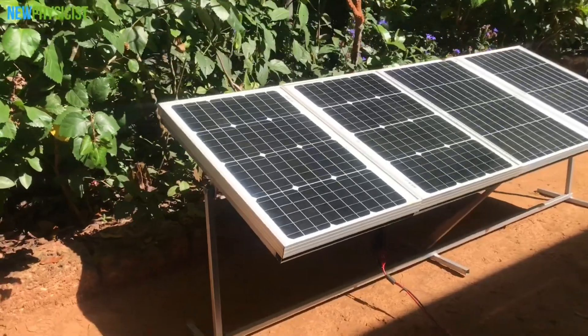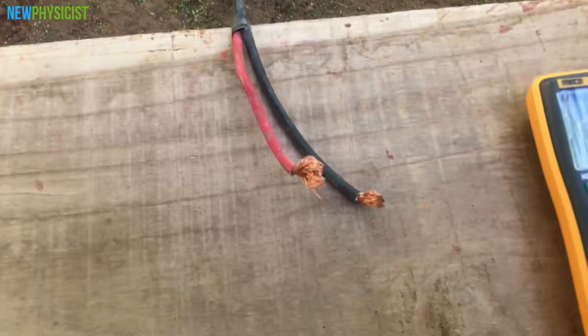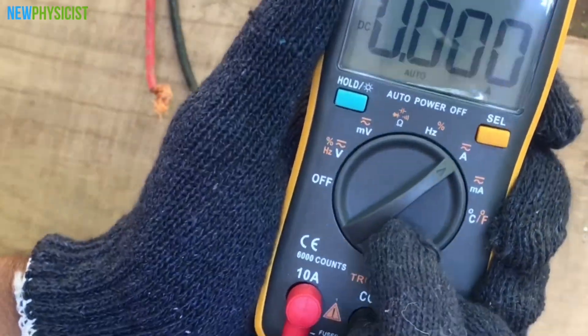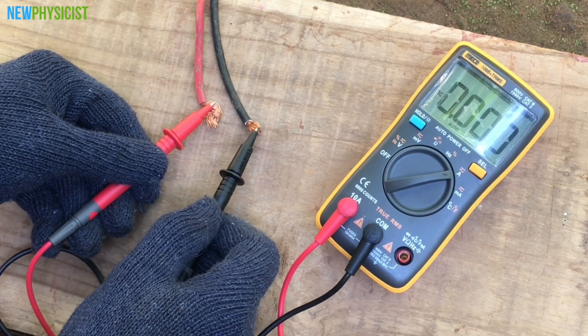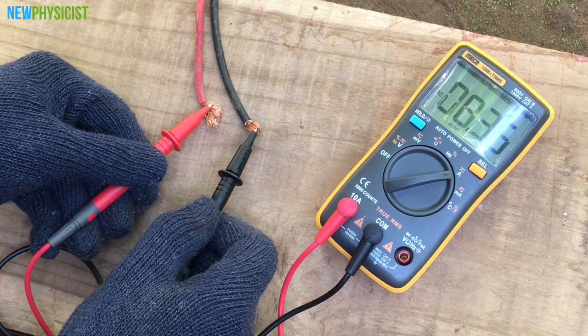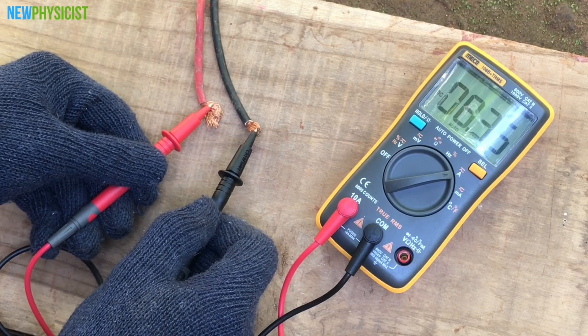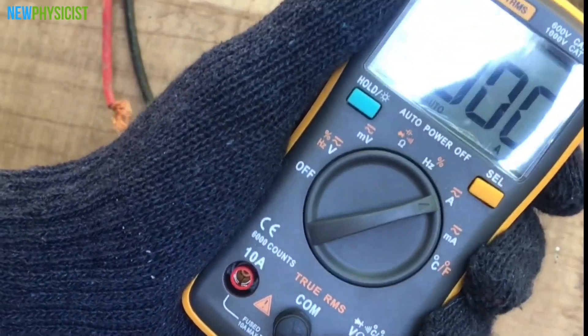Let's check the VOC and ISC of the solar array we just connected together. Adjust the multimeter to the 10 ampere range and then connect the testing leads to the solar panel output. When we are connecting our meter to a solar panel we are actually short circuiting the panel. This means the maximum current will flow through the circuit. Here we get an ISC of 6.3 amps.